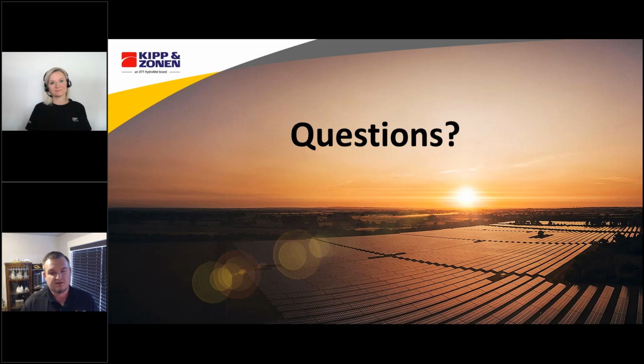I think so, and by tracker you probably mean the single axis tracker. My mind went to Solys 2 and tracking the sun's movement for direct and diffuse irradiance. A lot of single axis trackers have built-in tilt measurements to help control which angle they're pointing at. But this would be an external, third-party measurement that ensures the row you're currently measuring POA irradiance on is also tilting the correct direction. I could imagine a situation where the row with the pyranometer isn't the row with the tilt sensor, so the pyranometer ends up stuck at an angle while the rest of the rows on that same tracker motor are tilting correctly. It's a rare situation, but a big deal when it happens. So keeping that tilt measurement and cross-checking it against the actual tracker output could be a good thing to add into SCADA.